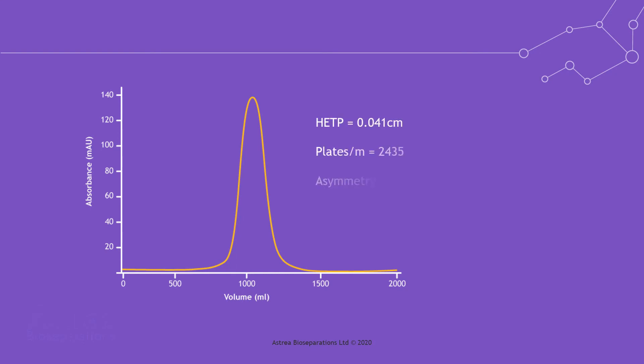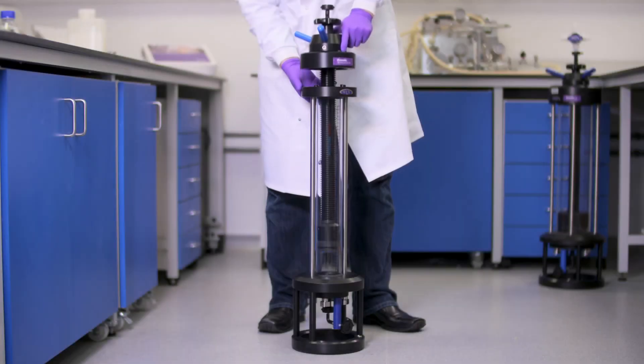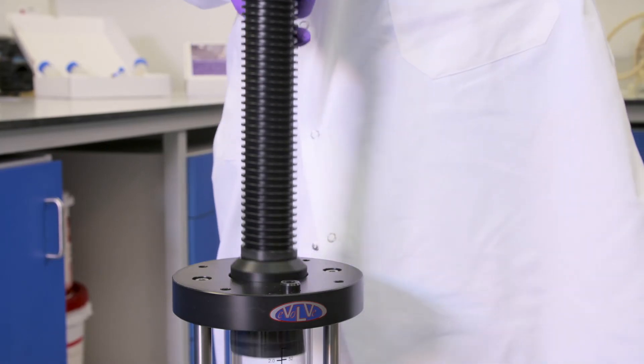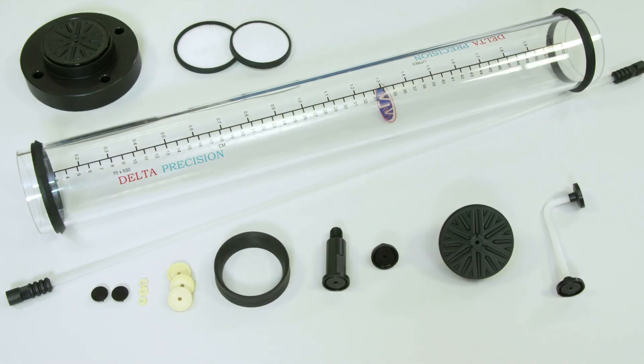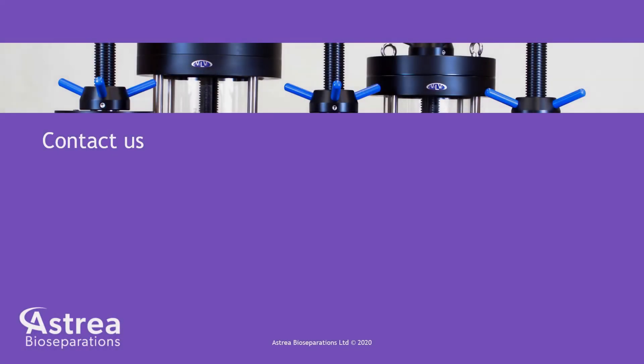To determine the quality of your packed column, measure the height equivalent to a theoretical plate and asymmetry by injecting a detectable marker. Astrea offers refresh kits for replacement of all the wetted parts of your used Evolve column, including the acrylic tube. This provides cost savings while eliminating the need to prove clearance of previous product and cleaning validation.